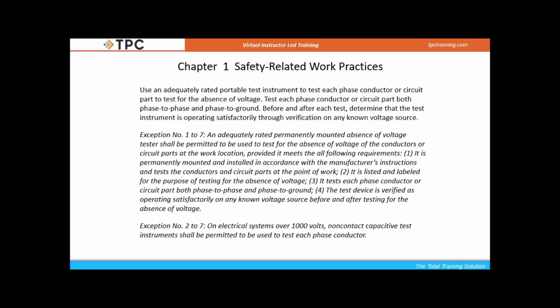And we're actually even going to be able to take a look at a little scenario with this after I've explained the whole thing. So first of all, they say this: use an adequately rated portable test instrument. If the voltage that we're working on is 1,000 volts or below, we are going to have a multimeter to do this. We are going to actually make contact with that circuit. And those meters are rated in 4 different categories, all the way from category 1 up to category 4, category 4 being the safest one we have.